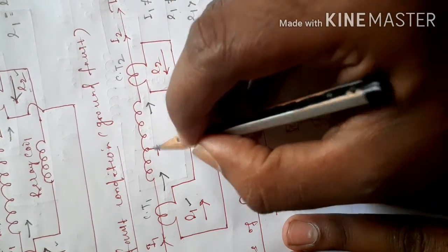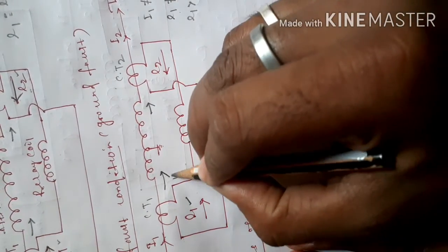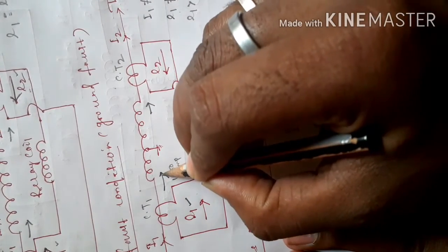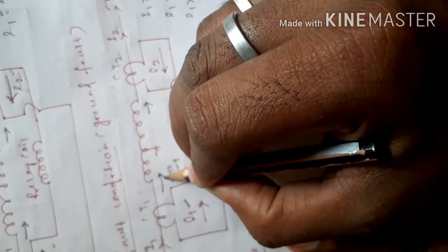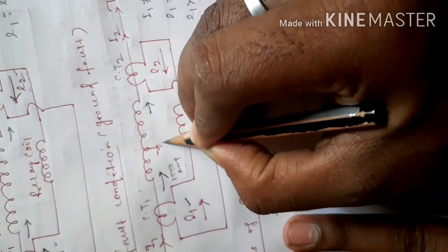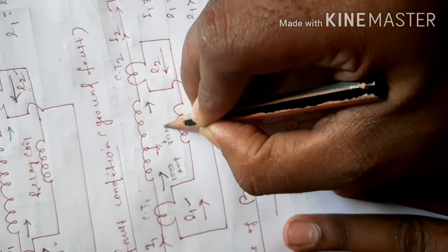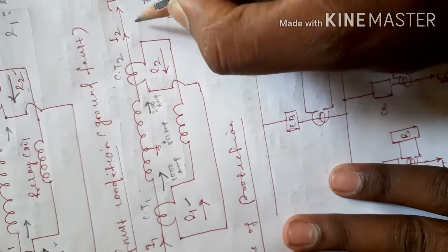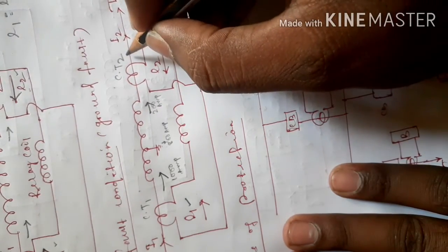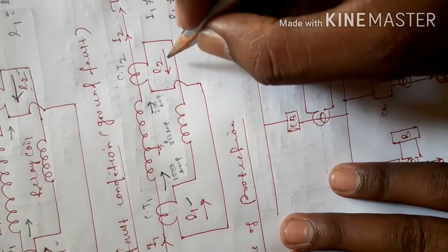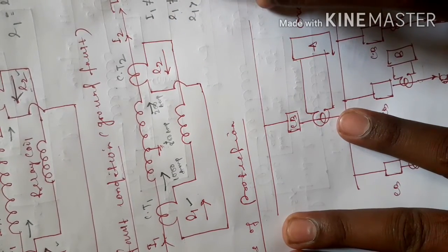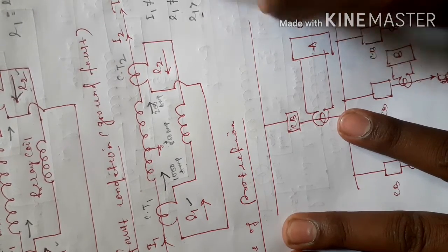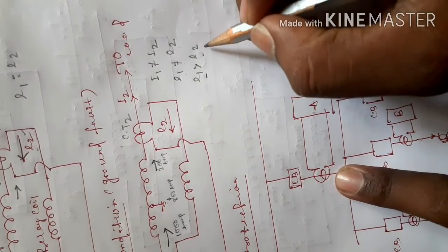Suppose a ground fault occurs and the incoming current is 1000 ampere. When a ground fault occurs, the current finds the shortest path. So approximately 4/5, that is 800 ampere of current, passes to the ground. The remaining 200 ampere is flowing to the load circuit, so the EMF induced on the CT2 side is less, meaning the magnitude of E1 is greater than the magnitude of E2.